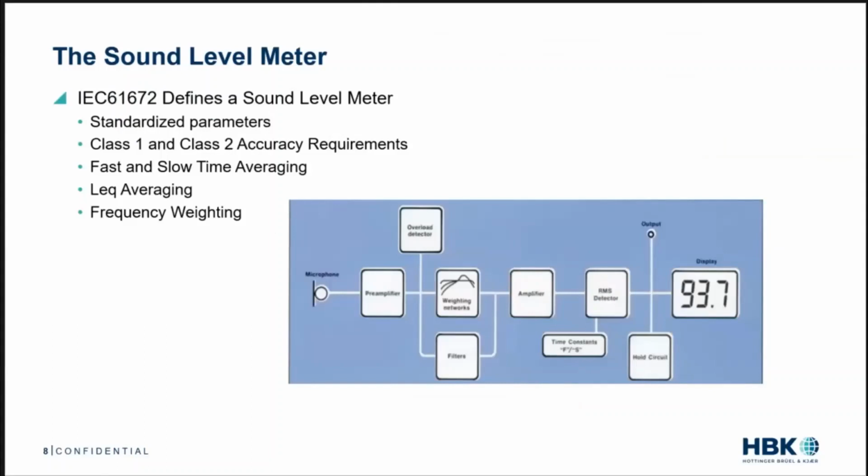The sound level meter is a tool that makes no aspirations to try to hear. Instead, it is a tool to assess the various standardized parameters of sound pressure variations in air. In doing so, with a qualified and calibrated instrument, the levels provided are governed within a certain tolerance, or more precisely, a precision. This precision and test methods are specified in the IEC standard 61672.